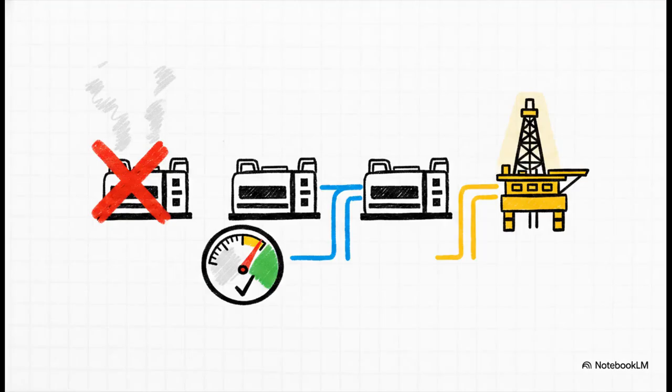Now, let's test our N-1 philosophy. Say we install 3 2,500 kilowatt generators, and one of them suddenly fails. The remaining 2 must carry that full 3,600 kilowatt load. The math shows our load factor spikes to 72%. That lands perfectly safely in our target zone of 70 to 85%. Disaster averted, and the lights stay on.